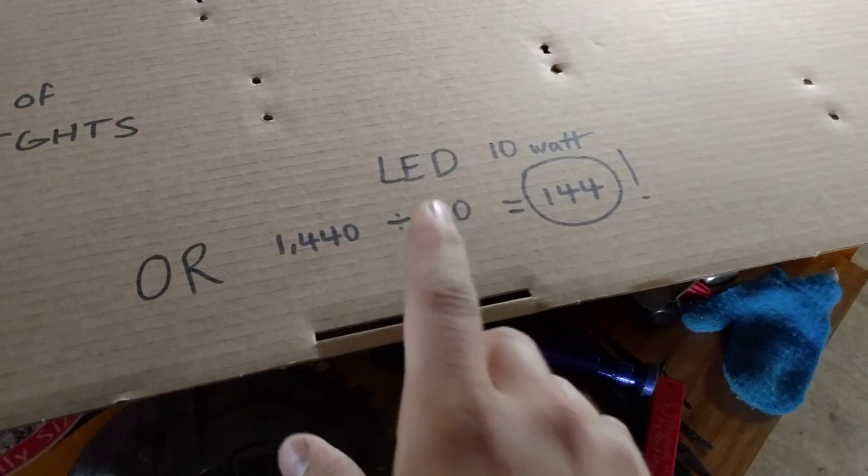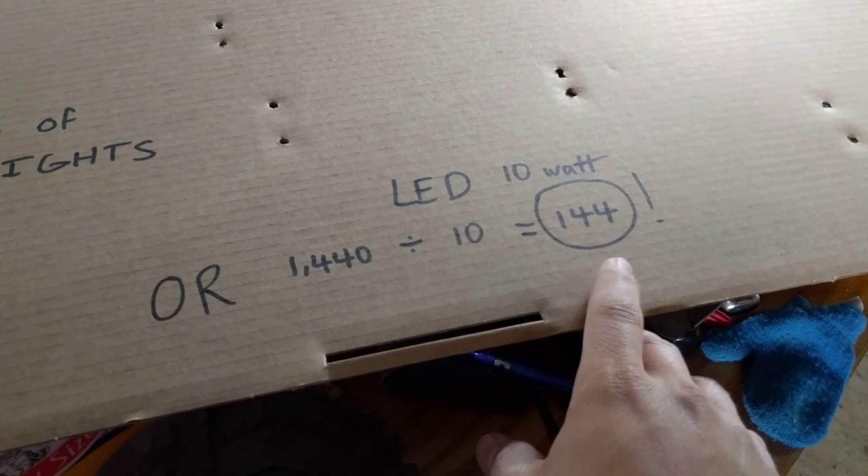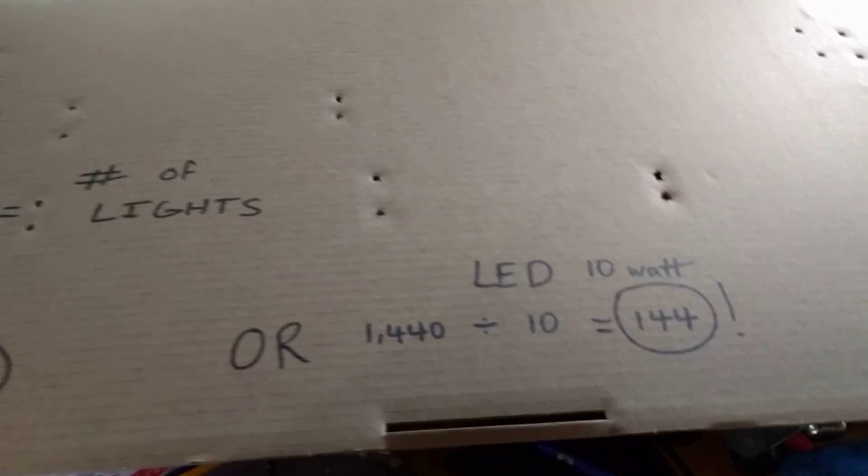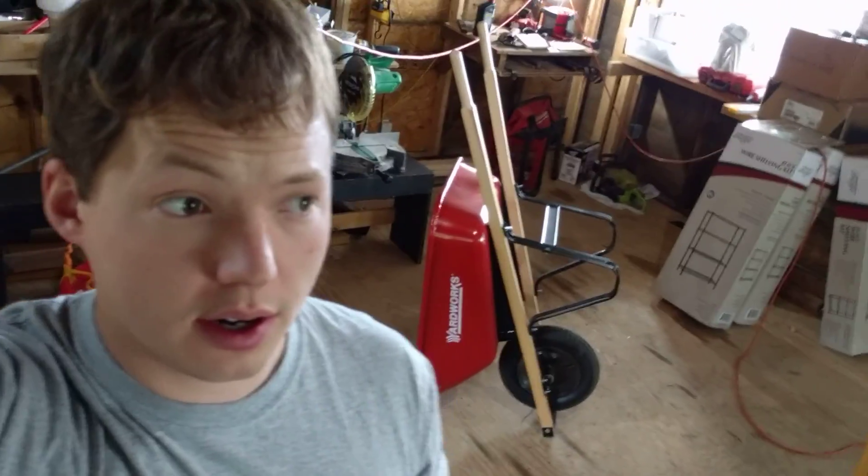The thing that's a big factor right now is that everything is going to LED, switching from 65 watts to maybe 10 watts. Some of the bulbs I already got are 9 watts even. So interestingly, if these were LED drawing 10 watts, you could put 144 light fixtures on one 15-amp breaker — which means one 15-amp breaker could do my entire house for lighting if I put in all LED.